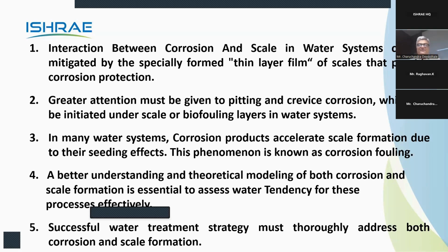So greater attention must be given to pitting and crevice corrosion, which can be initiated under scale and biofouling layers in the water system. If you allow scaling to take place, a lot of issues will occur in the condenser or in our system, and ultimately what we lose is energy.